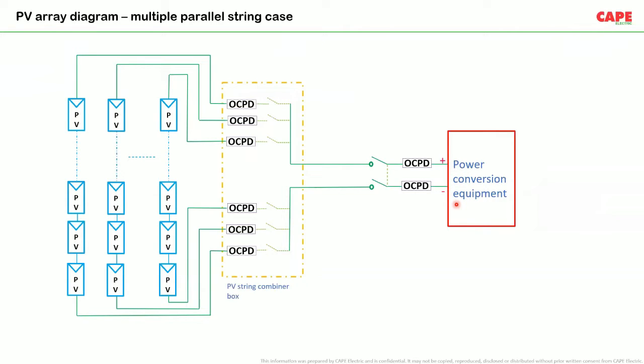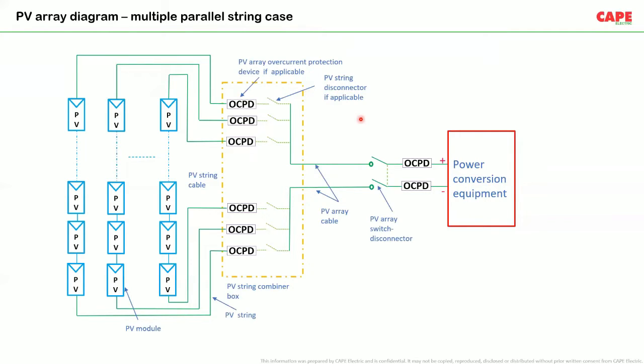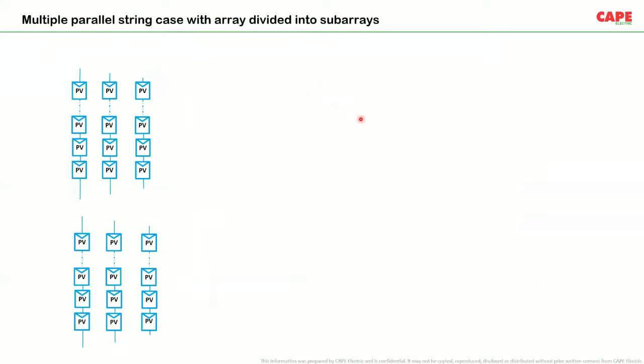Normal people shall not go to those areas. Now, again, some more explanations. PV modules are connected in series, PV strings are made, then combiner boxes are there. These boxes are collecting the energy, and normally contain fuses, SPDs, isolators, and so on. Finally, they are connected to the power conversion equipment. Some of the definitions you can also see here: PV overcurrent protection, PV string disconnector. All these are sometimes written as 'if applicable'. So it's very interesting to note that these are 'if applicable'. I will explain it later.